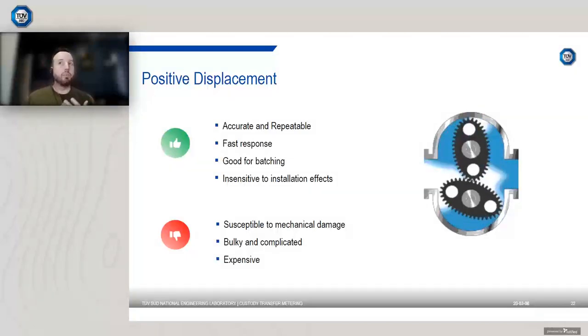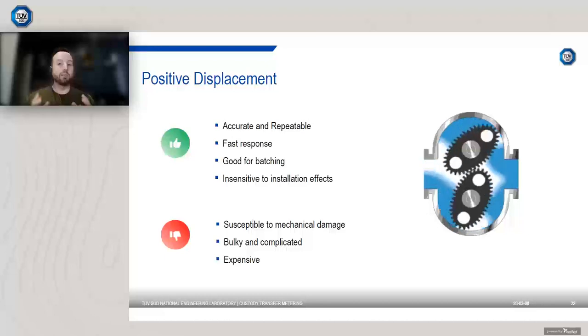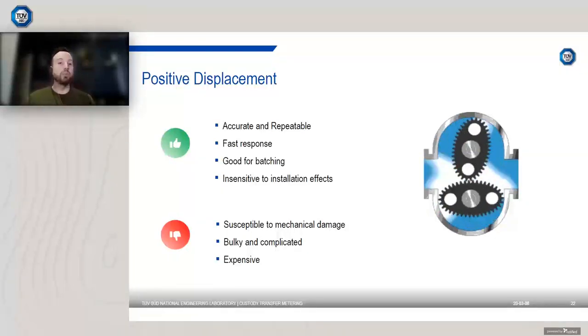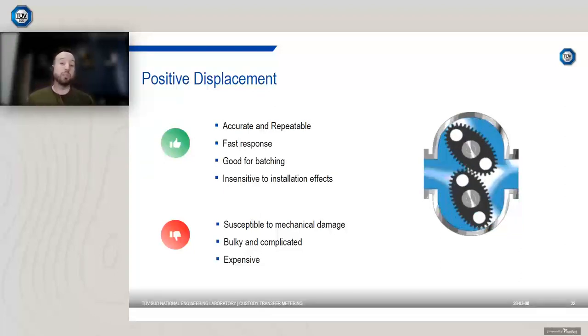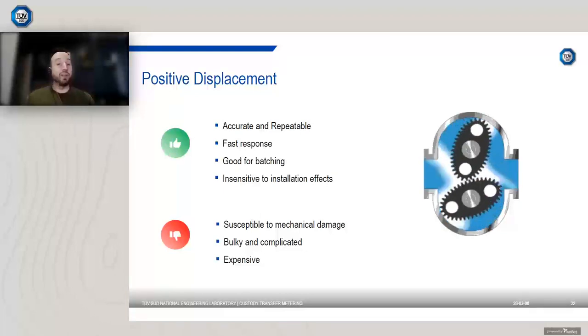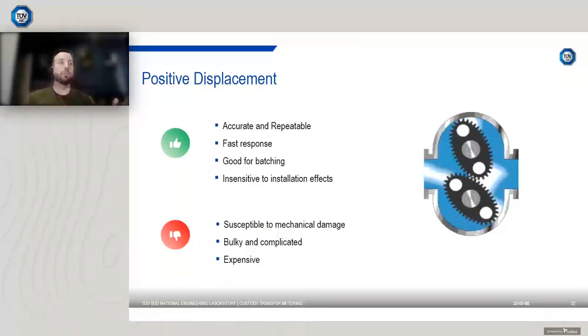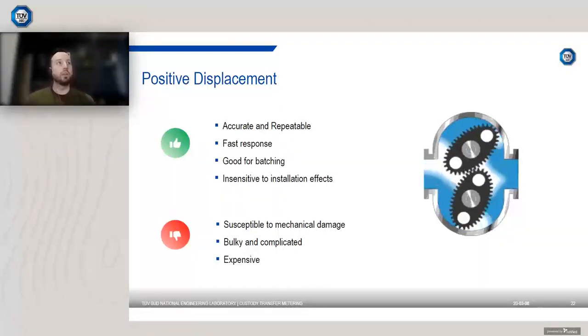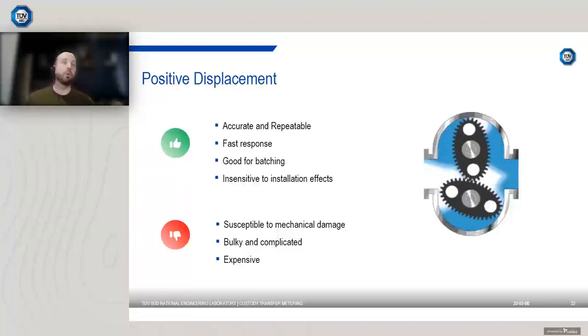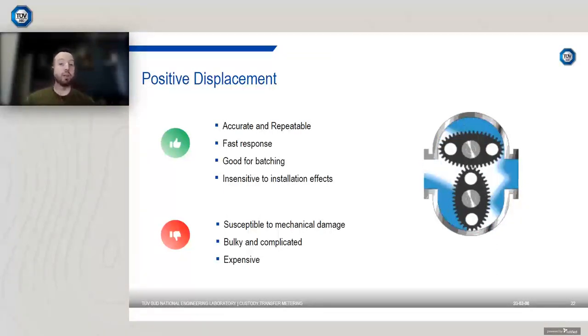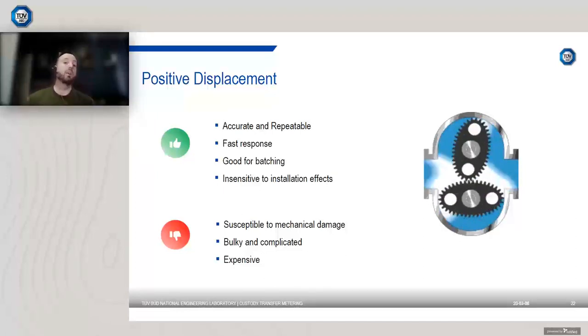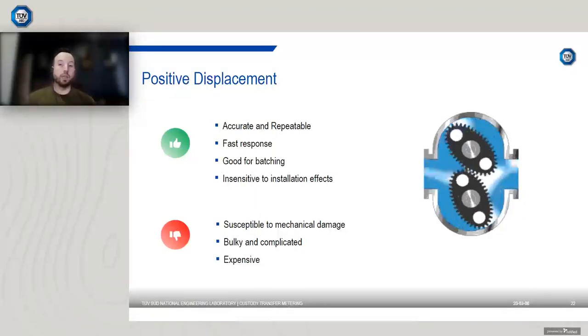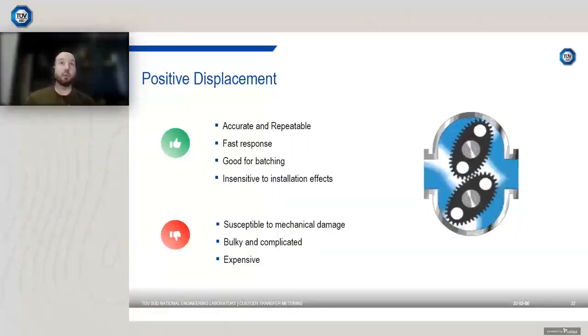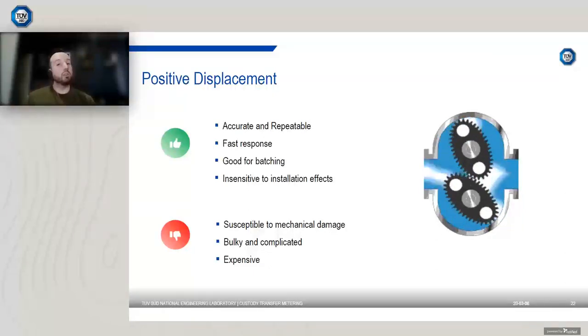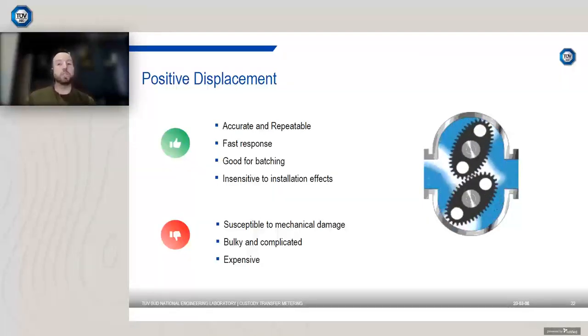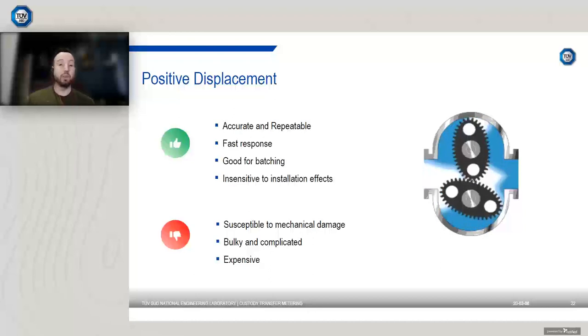Now, because this is like a direct measure of flow, you're directly capturing a fixed volume. They tend to be very fast responding meters. They are accurate and they can be very repeatable depending on their design. One of the biggest advantages is they're insensitive to installation effects. So orifice plates, turbine meters, you need a nice fully developed flow profile. Usually means you need a certain amount of straight pipe or a flow conditioner. Positive displacement meters don't require that. So if you know you've got significant installation effects, positive displacement meters are a good choice. And they've been used as master meters to verify other flow measurement technologies. Downsides are they're susceptible to mechanical damage, again, moving parts, tend to be quite bulky and complicated devices, and they can be expensive as well.